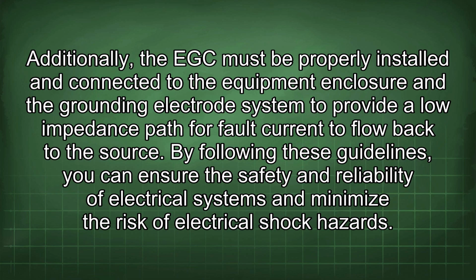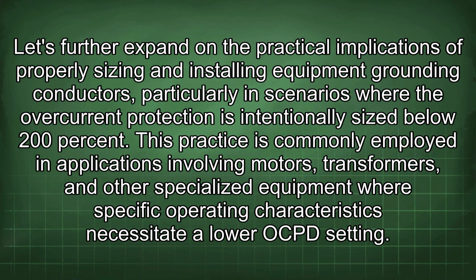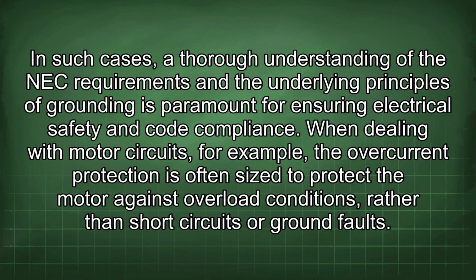Let's further expand on the practical implications of properly sizing and installing equipment grounding conductors, particularly in scenarios where the overcurrent protection is intentionally sized below 200%. This practice is commonly employed in applications involving motors, transformers, and other specialized equipment where specific operating characteristics necessitate a lower OCPD setting. In such cases, a thorough understanding of the NEC requirements and the underlying principles of grounding is paramount for ensuring electrical safety and code compliance.